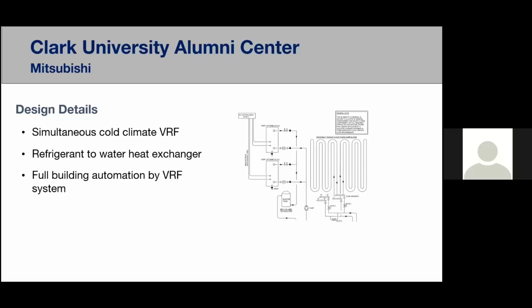The cafeteria, which is actually right here in this glass building, stood 2 floors tall. It was going to be tough to get some heating capacity over there. So what we decided to do is connect these hex units, or water heat exchangers. So it's refrigerant going from the condenser to these hex units, exchanging heat to a water loop. And this water loop was a low temp hot water that was giving off radiant heat to that cafeteria space. Now, the cafeteria space also had an air handling unit on the 2nd floor. So basically, through controls, these systems were not fighting against each other; one was on or the other was on, and we made it work that way.